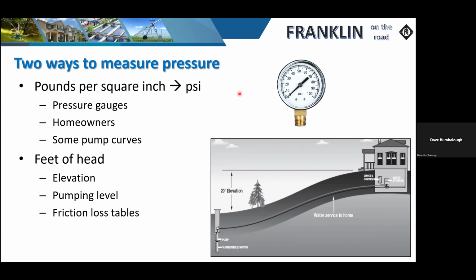PSI is typically measured with a pressure gauge. And honestly, it's more just to see what the system is doing and how it's operating. We can also convert that to feet of head, and I'll show you that conversion here in just a second. But feet of head is basically the equivalent to that. When we're looking at feet of head, we're basically looking at the elevational changes from where the water is in the well to where its point of discharge is going to be, pumping levels included in that, along with any kind of friction losses. And we'll cover all those as we go through the next few slides.